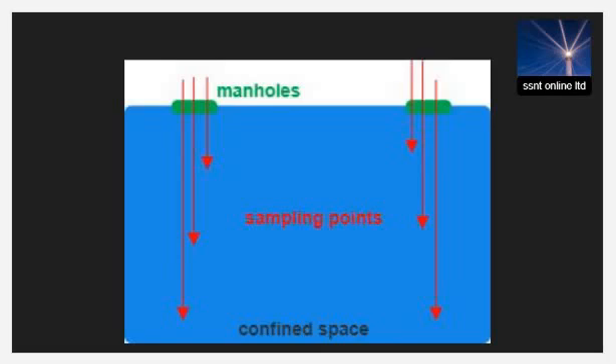For each test required on the permit, you must allow enough time for the air from the space to be drawn into the equipment and for the sensor or other detection device to react to the chemical if it is present. This is considered the minimum response time, noted by the manufacturer in the operator's manual. Be aware that additional time is needed if hosing or a probe extension is attached to the inlet, to allow air from different depths to be pulled in. If a sample probe is used, it will have to be purged between samples.